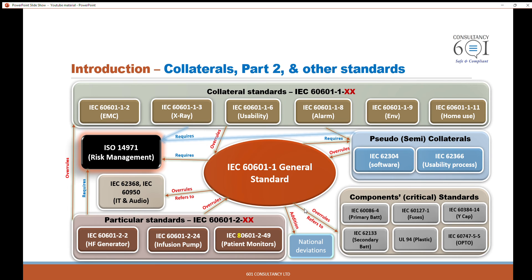The other term is refers to. The general standard refers to the component standard and also refers to the IT standard. IEC 60601-1 also uses the IT and audio standards for other areas such as insulation coordination. It depends really on the route of compliance or the route of testing.